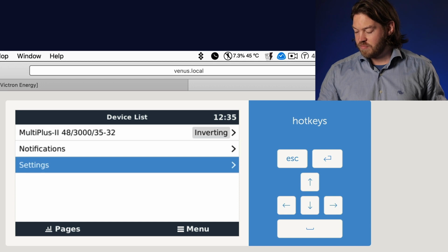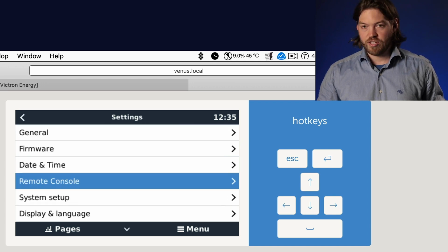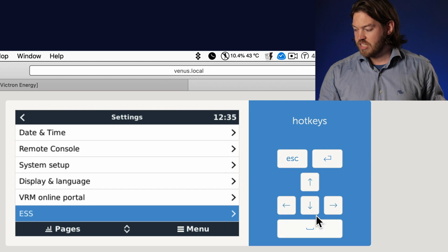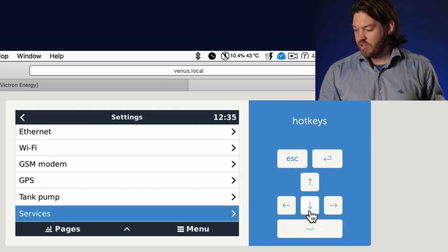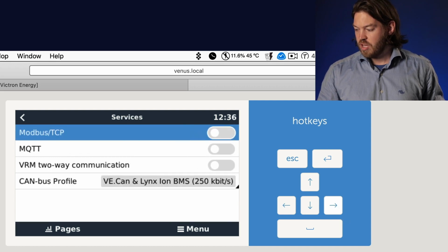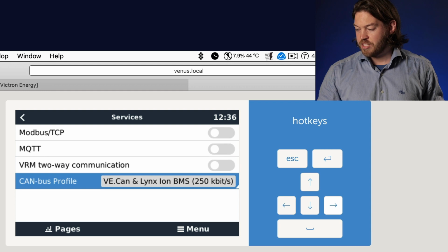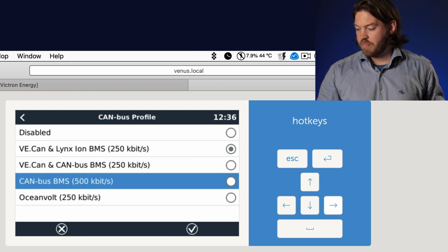We need to make some configuration changes so that it can find the battery. By default, these VE CAN ports are set to VE CAN 250 kbit/s. We need to go into the settings and scroll down, either using the arrow keys on the computer or selecting the down arrow with your phone. Let's go to the very bottom where it says services, then along to CAN bus profile, and select CAN bus BMS 500 kilobits per second, selecting that with the spacebar or by clicking this button here.